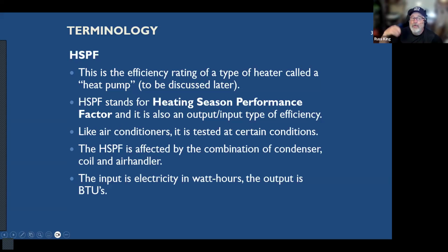Again, it's how much you're getting out for how much you're putting in. What we're getting out of a heat pump is heat in BTUs per hour. What we're putting into it is electricity. So we want a lot of heat out of it for the amount of electricity that we're putting in. And they test this at certain conditions. Like air conditioners, the HSPF is affected by the condenser and the coil and all this other stuff. So, a little preview of what we're going to talk about: a heat pump is basically an air conditioner that runs backwards in the wintertime.